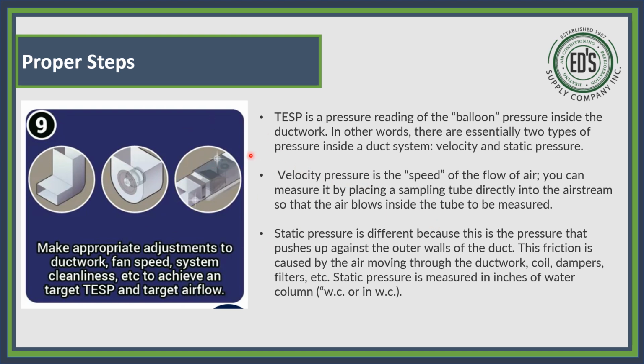All right, and then you look at here, the proper step. Make appropriate adjustments to the ductwork, fan speed, system cleanliness, etc., to achieve a targeted TESP, which is total external static pressure, and target airflow. So TESP is the pressure reading, which is your resistance inside the ductwork. In other words, there are essentially two types of pressure inside a duct system. There is velocity and static.